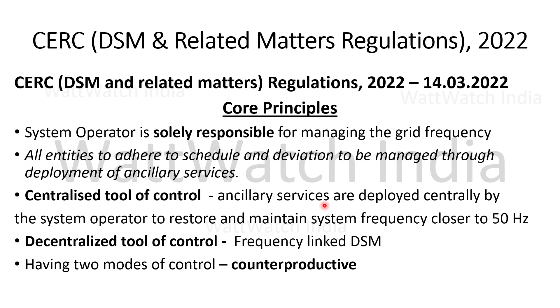Now, another thing, if we look at the frequency plot of 1st of September 2009, which is prior to these deviation mechanisms, we can see the excursions in the frequency, how high and how low they are. But now with improvised and evolved regulations, we can see in the plot of September 2020 that the excursions in frequency, the variations over the baseline of 50, are not simply high enough. So earlier, the frequency was an indicator of under or oversupply.